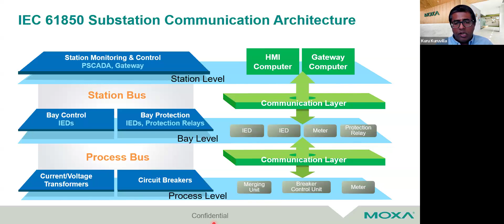Because most things on a power grid can be derived, if you will. If you know the voltage, you know the current, you know the frequency, you derive things like phase angle, and you derive things like differentials of currents and rate of changes and so on. So the sampled measured value is a standardized way of collecting digitized measurement data, and that data is sent primarily into the IEDs, typically protective relays, and those relays make a decision, and they send a command.